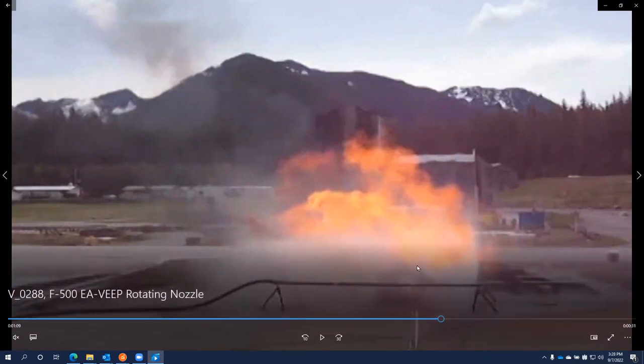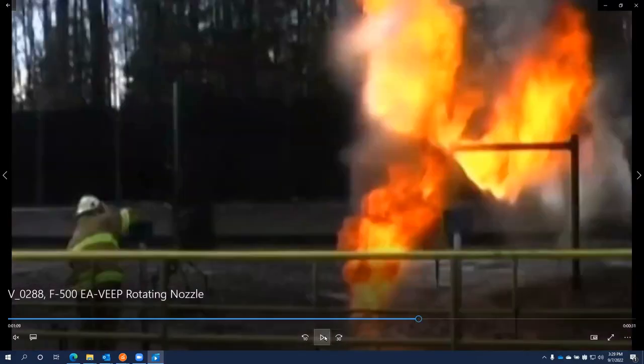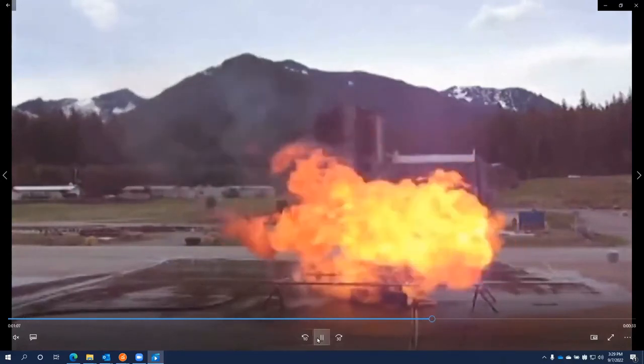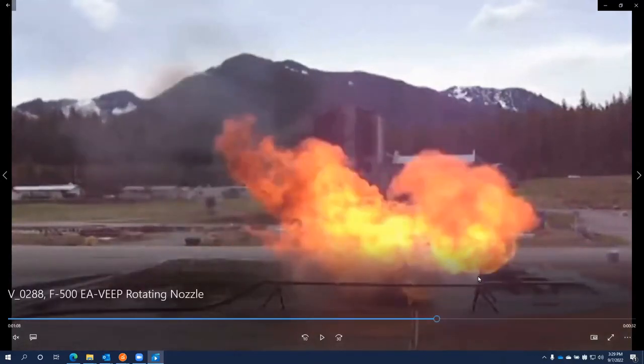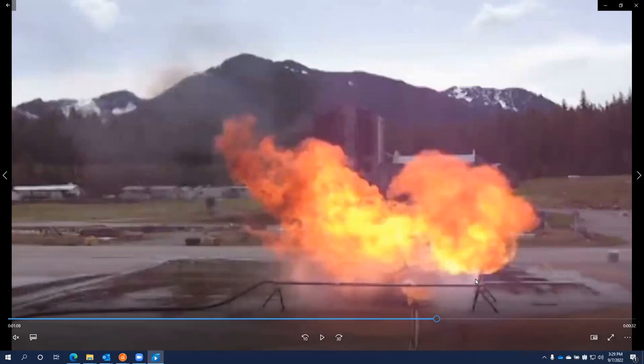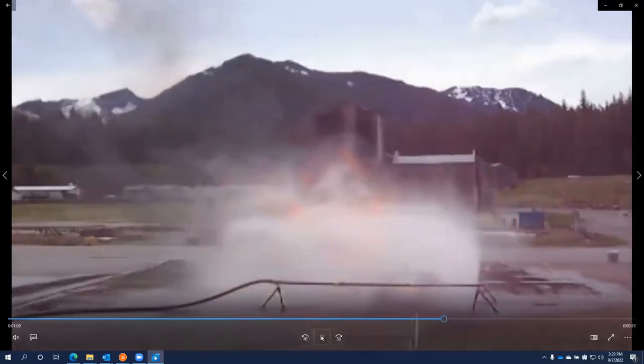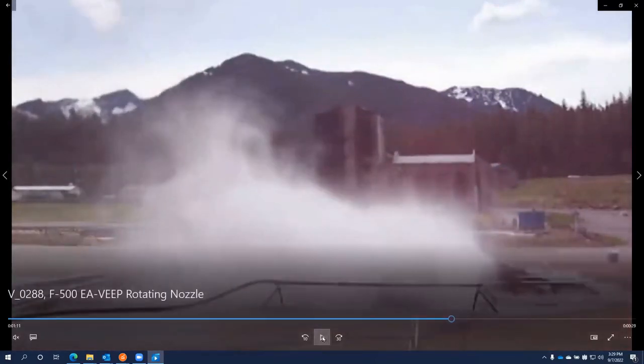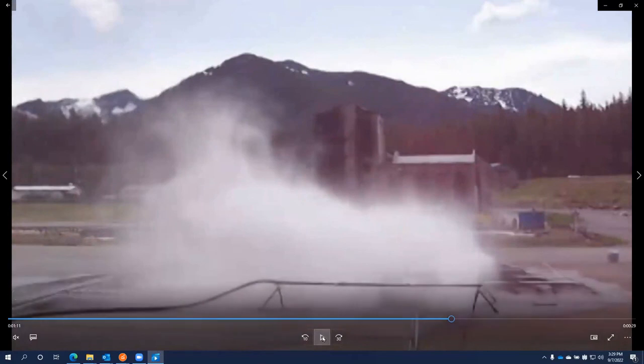You see, we still have the flame, so we still have high heat, but none of this is on fire back here. Prior to the encapsulator agent, the flame was igniting everything coming out. The minute we start to apply the agent, we start to encapsulate the fuel coming out, so it's no longer flammable and no longer ignitable. We're able to extinguish this, but it was this 3 seconds of video that gave me the brainchild.